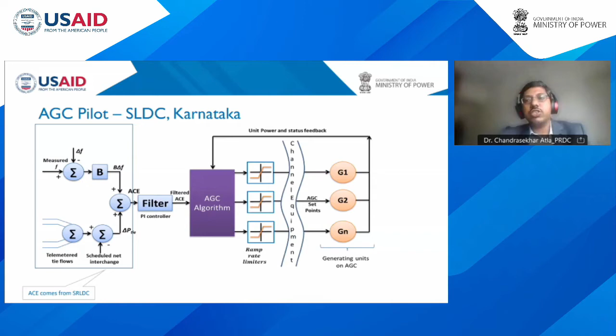During the Go Live, which we did in December for the Sharavati Hydro Plant and in January for the Varahi Hydro Power Plant, we mapped the AGC signals and tested the two-way communications, first at the unit level and later at the plant level. An important point is that full control will be with the hydro plant operator as the master control, because that is very much required. He knows the plant side constraints. Once he enables the AGC, the system operator can take control. It was observed during the go live that the response of the hydro units was in line with the AGC response asked by the LDC.